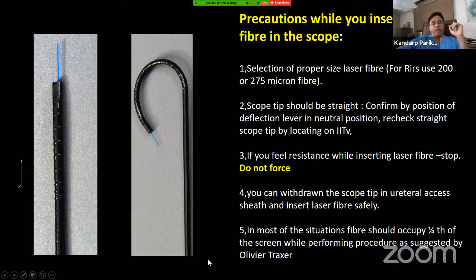Now, what precaution will you take when you are inserting a laser fiber in an accessory channel? The first important thing is that you have to select a proper size laser fiber, 200 micron or 270 micron fiber, depending on the size of the stone. Second important thing is that whenever you are inserting a laser fiber, the tip of the scope should be straight like this. If the tip of the scope is flexed like this, and if you insert the laser fiber like this, it will break the accessory channel and your scope is gone. So always make sure that the tip of the scope is straight.